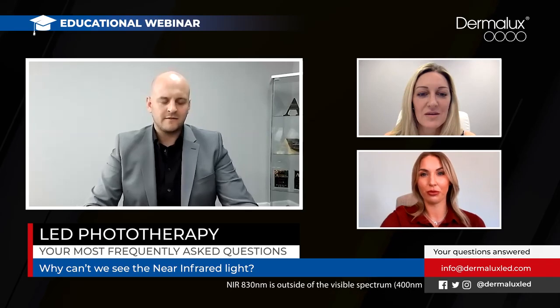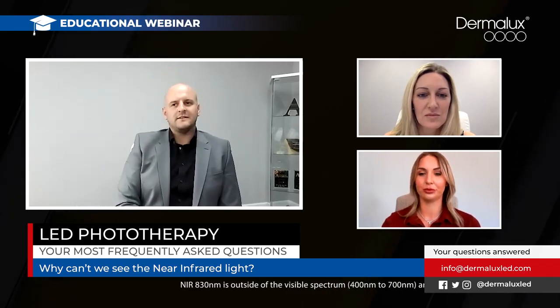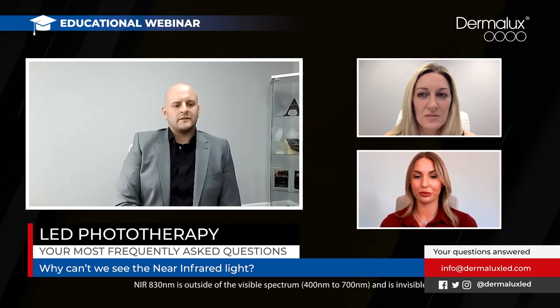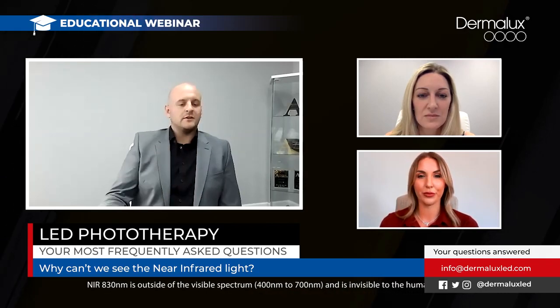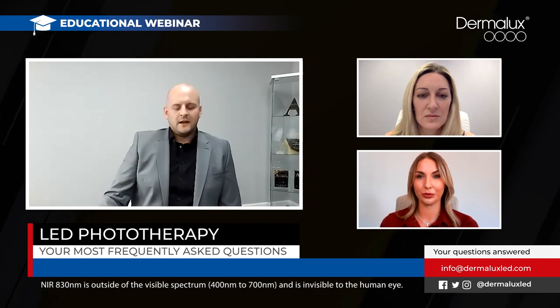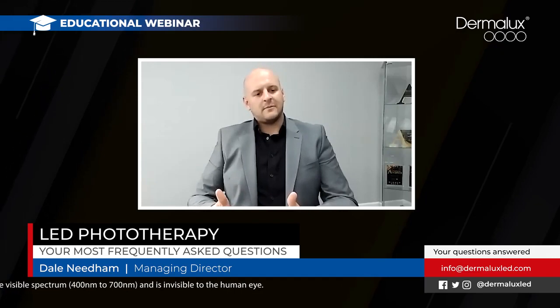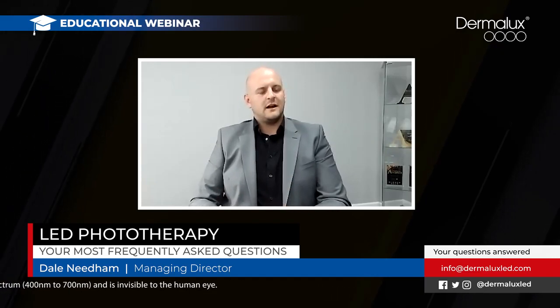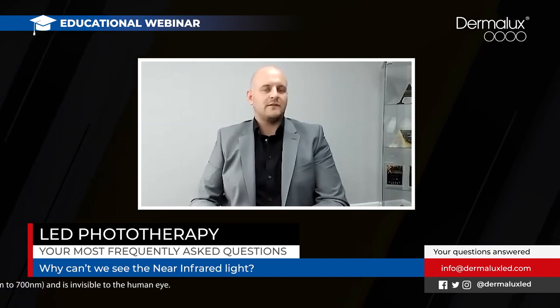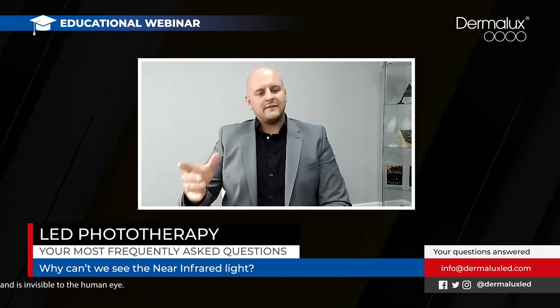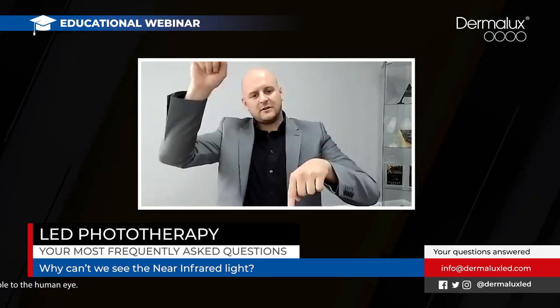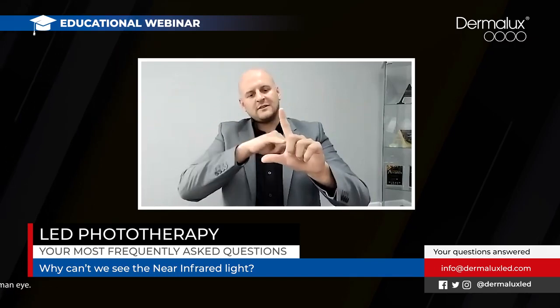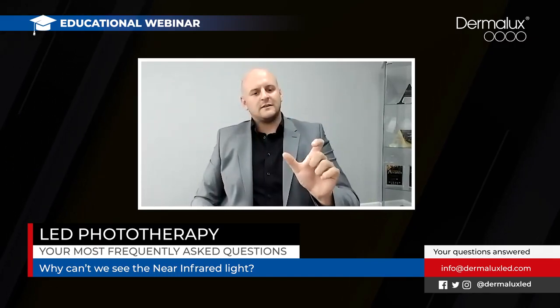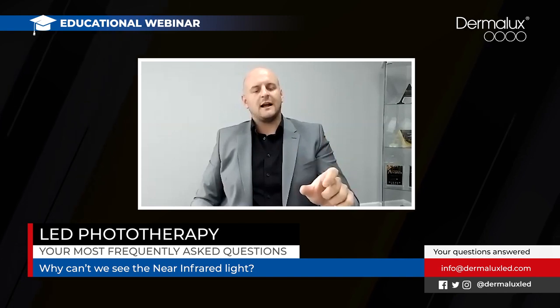Infrared, it depends on the manufacturer as to whether you can see the infrared or not. And the reason I say that is it comes down to the quality of the LED that's being used in the device, which is meant to be emitting infrared light. Earlier I spoke about having a very narrow full-width half max, which is true across all of our wavelengths that we use in our device. Because of that, if you're emitting a true infrared at 830 like we are, with a very narrow full-width half max, even at the short wavelength boundary, going back to this distribution of the curve again, because it's so narrow, even on the tail end of the emission, it's not within the visible spectrum, so you won't actually see the LED light emitting light.